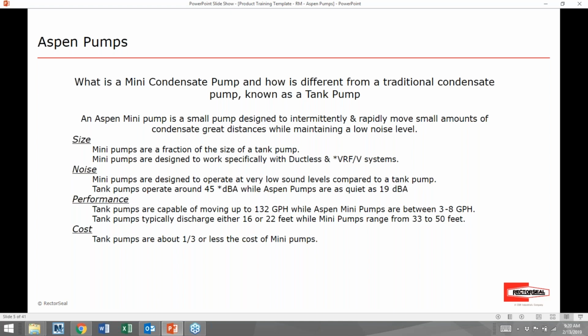Tank pumps, on the other hand, can only typically discharge water either 16 or 22 feet. Those are the two typical standards in the tank pump segment of this business, while mini pumps can pump 33 feet and our maxi pumps up to 50 feet. And then cost. Tank pumps are very, very inexpensive compared to a mini pump. They're very simple machines. The mini pump is a much more engineered product, requires much tighter tolerances, and therefore drives the cost up.